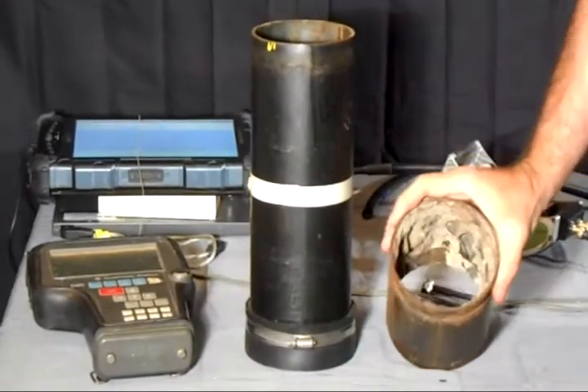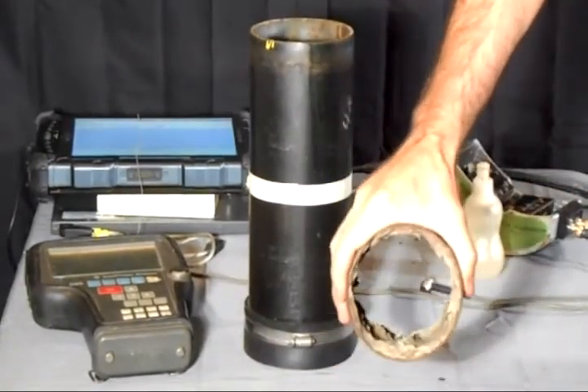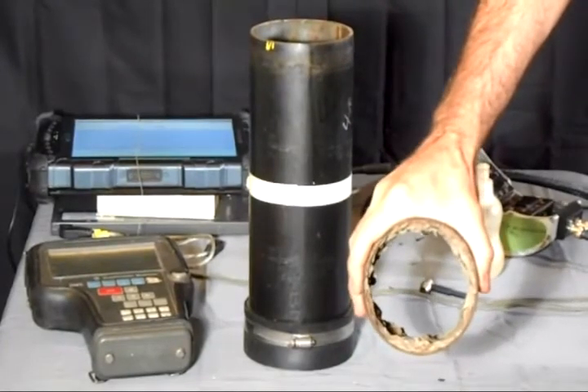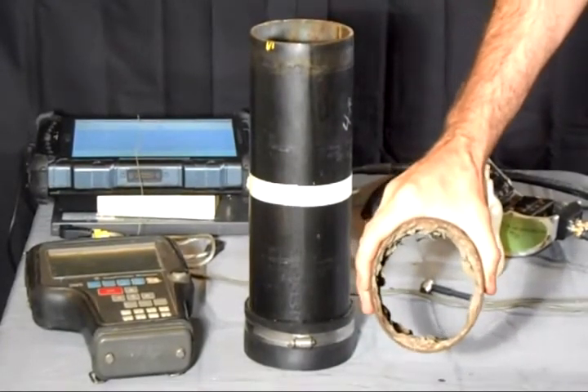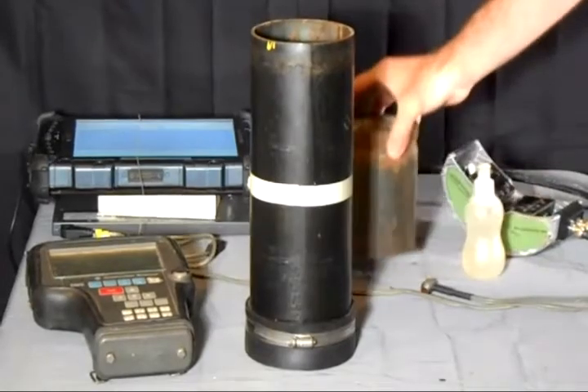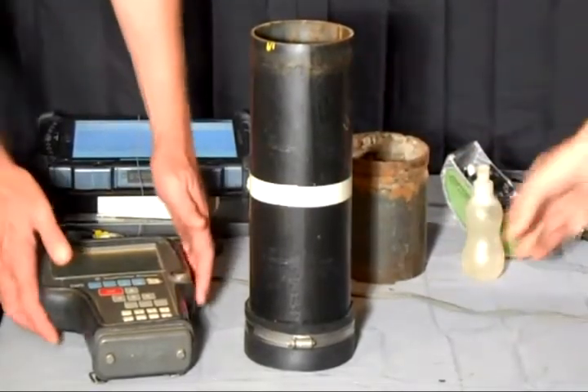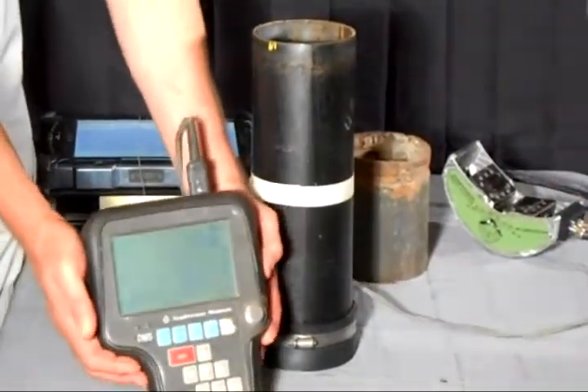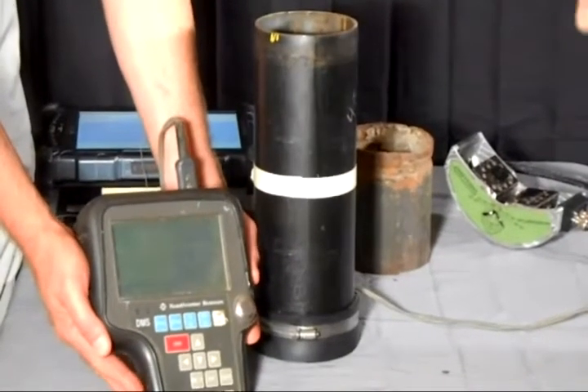This one, exact same type of pipe, both 4-inch Schedule 10 steel fire sprinkler pipe. This one obviously is corroded on the inside. So what we're going to do is start off with thickness test. What we've got here is a standard thickness gauge.